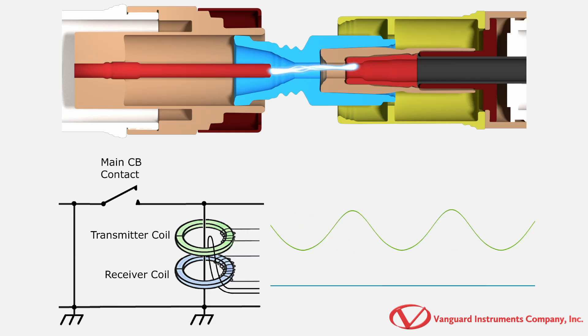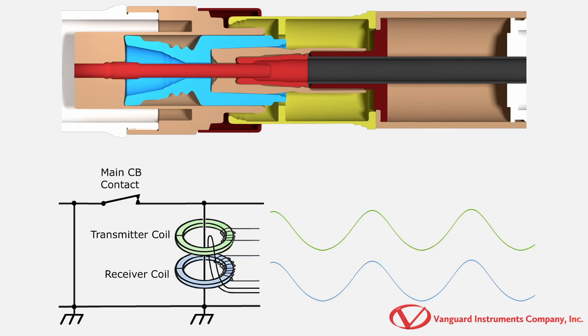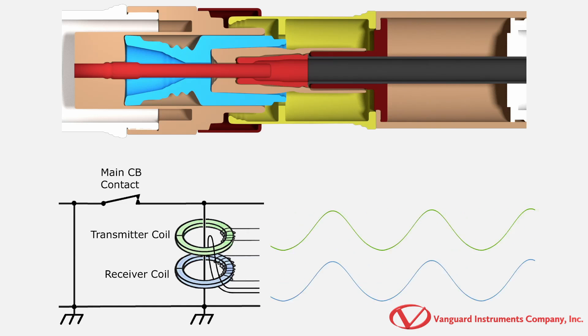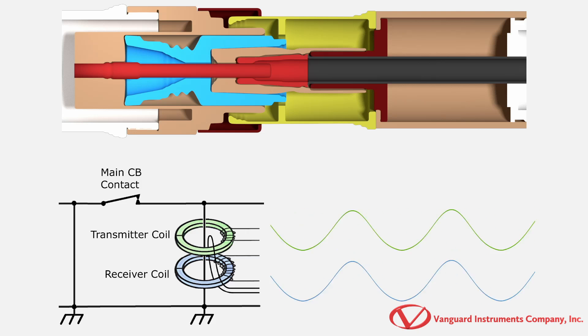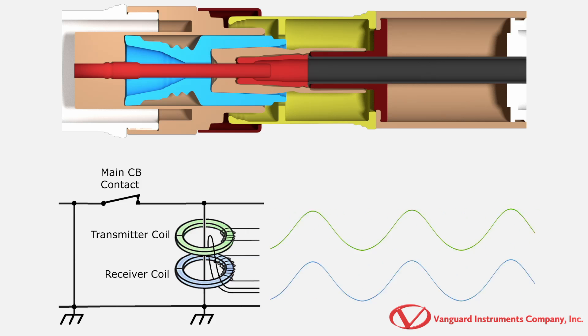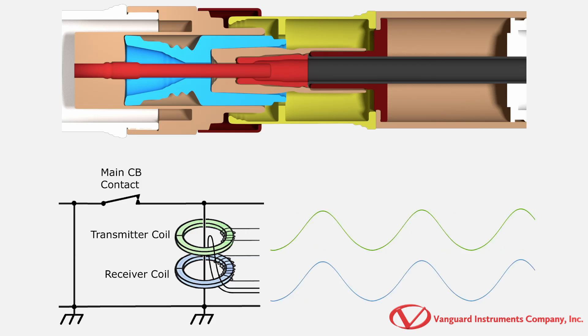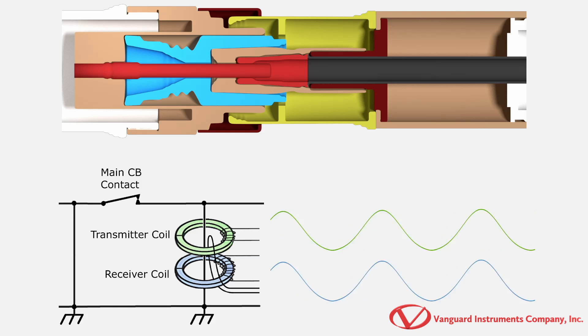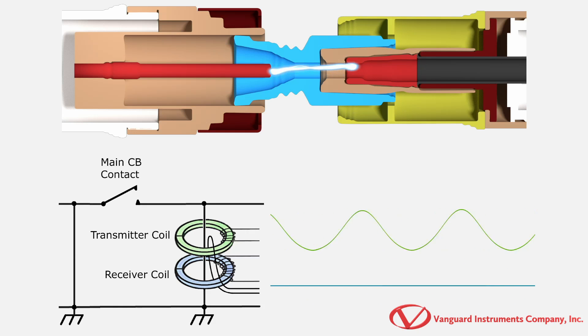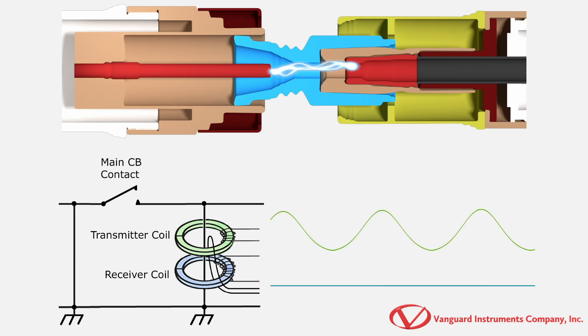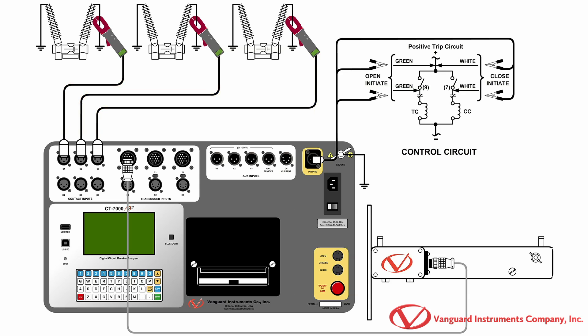If the main contacts are closed, this high-frequency voltage signal will cause high-frequency current to flow through the ground loop and closed circuit breaker main contacts. When the circuit breaker's main contacts open, the closed ground loop is broken and the measurement probe's receiver senses the loss of the current signal. The receiver's signals are sent to the Vanguard circuit breaker analyzer and the algorithm in the unit computes the circuit breaker main contact open and closed times.